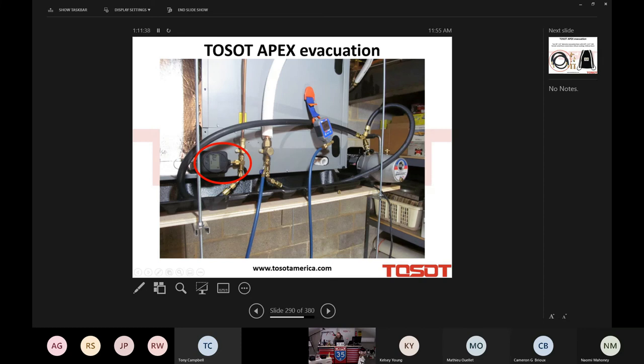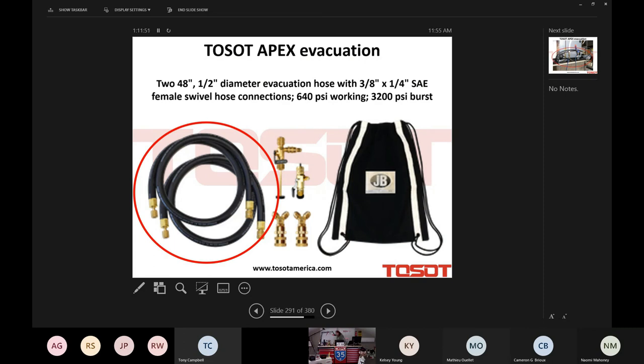Again, a hose not designed for a vacuum, right? And the gauge a fair distance from the source of the vacuum. This is ideal. This is not. Look at the size of the hoses, guys. The physical dimension, the diameter, is very different, much larger than what comes on a standard manifold gauge set. And also look, it's not red, yellow, or blue, right? The molecular makeup of this hose is that it is not porous. It is designed to hold a vacuum, right? That's the beauty of that product.